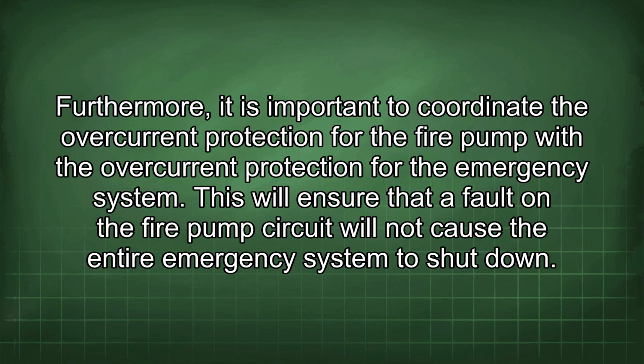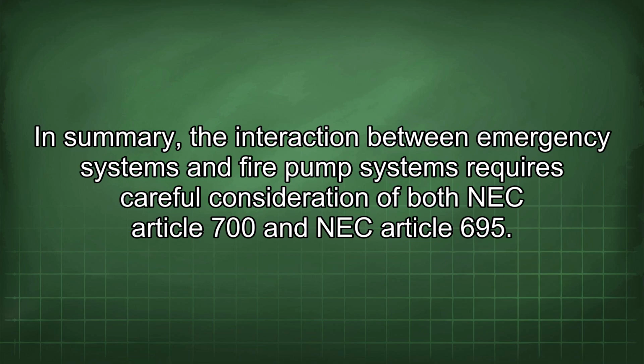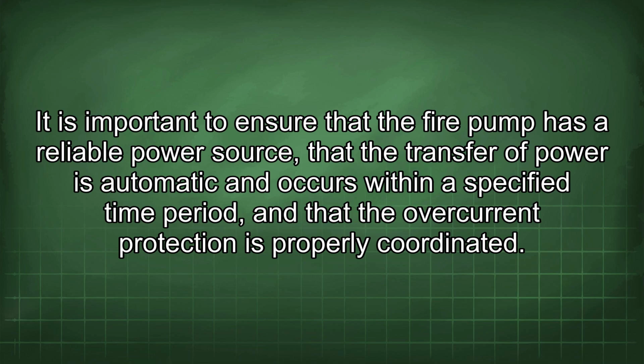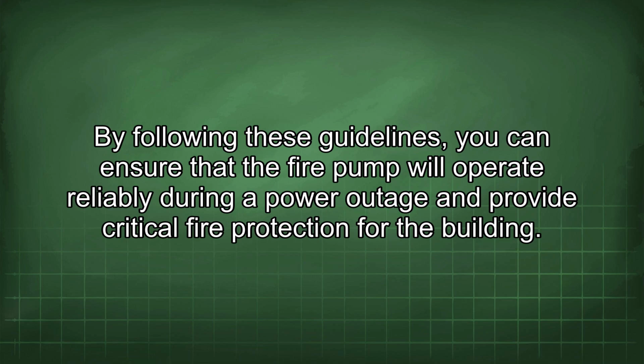In summary, the interaction between emergency systems and fire pump systems requires careful consideration of both NEC Article 700 and NEC Article 695. It is important to ensure that the fire pump has a reliable power source, that the transfer of power is automatic and occurs within a specified time period, and that the overcurrent protection is properly coordinated. By following these guidelines, you can ensure that the fire pump will operate reliably during a power outage and provide critical fire protection for the building.